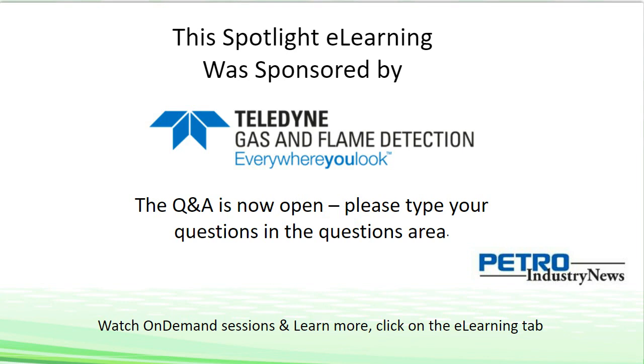And when placing a fixed gas detector, consideration of the most likely gas that's going to leak, or the gas that you're actually looking for in terms of a leak, the main hazard, may say whether the detector should be fixed above or below where the leak point is going to be, or you fix one sensor that's looking for hydrogen above and another sensor that's looking for a different gas below. So these are also, the relative densities of the gases that are leaking, which is driven by the molecular weight of the gas, and also the temperature, are also relevant considerations for the optimal siting of the fixed gas detection systems.